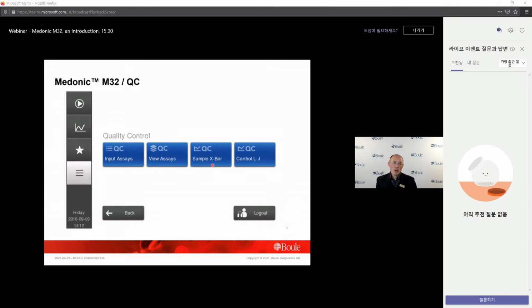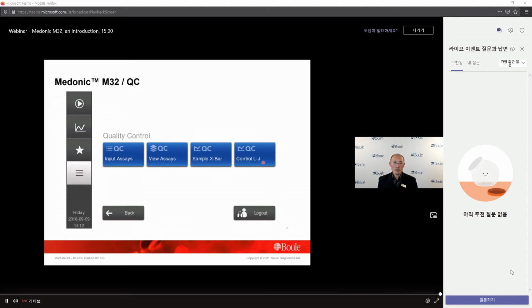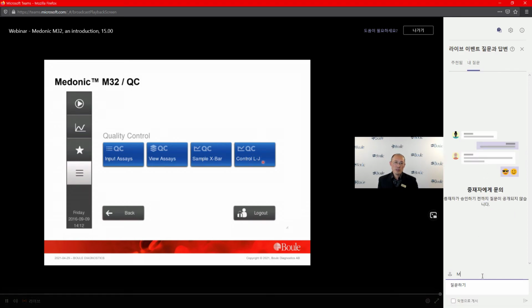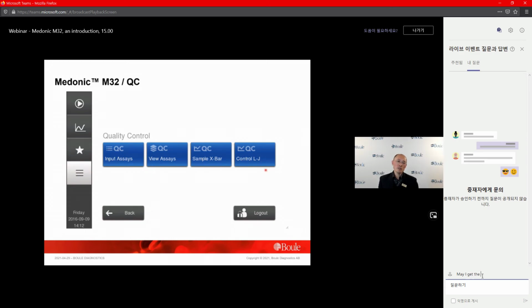The sample X-bar uses sample results, three major parameters which are quite stable for all samples: MCV, MCH, and MCHC. So these three parameters are quite stable for all human samples, for long-term monitoring of the instrument stability. And for control blood, there is a Levey-Jennings plot for each lot number of the controls, and many parameters are monitored.